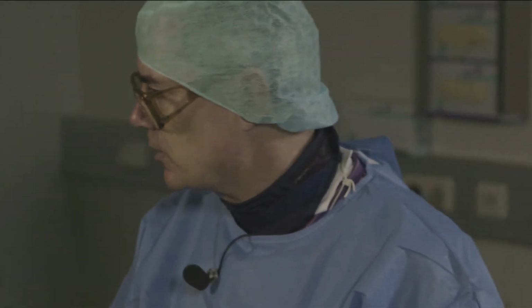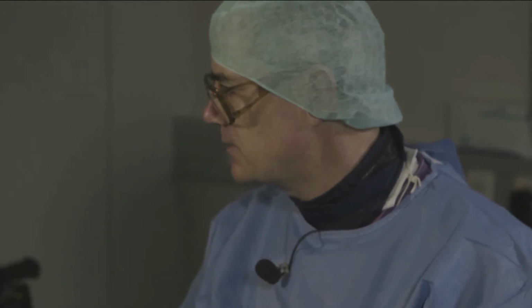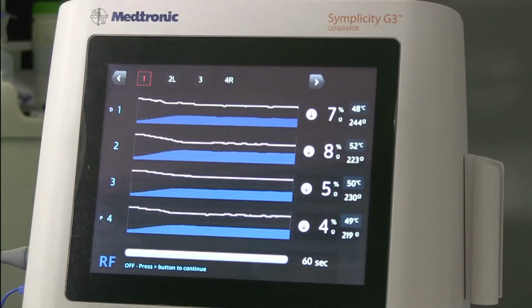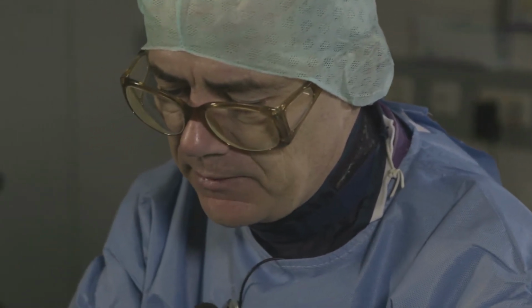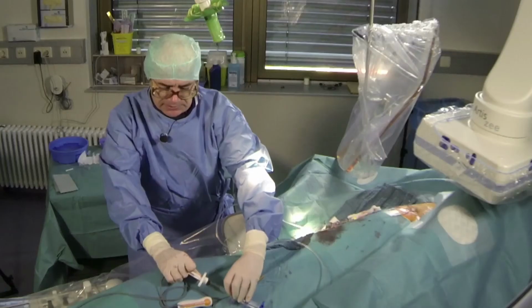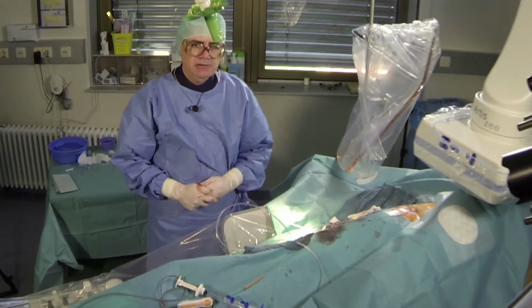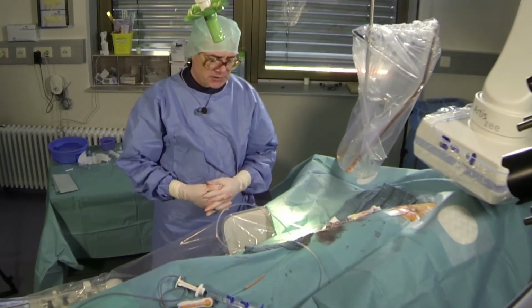Now we have a nice drop of the impedance again, but overall we had a significant increase of temperature. We had a decrease in the impedance, and like with the Flex catheter, there's an algorithm implemented in the generator that stops the radiofrequency energy application in case there is insufficient drop of impedance or insufficient increase of local temperature.